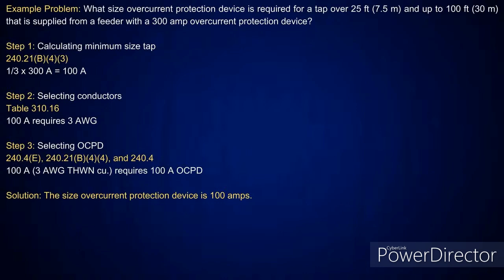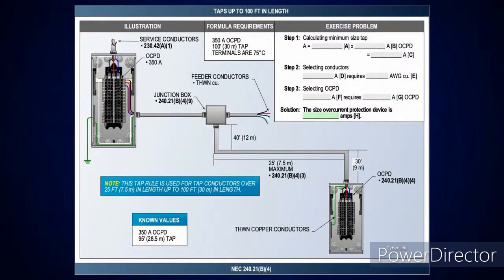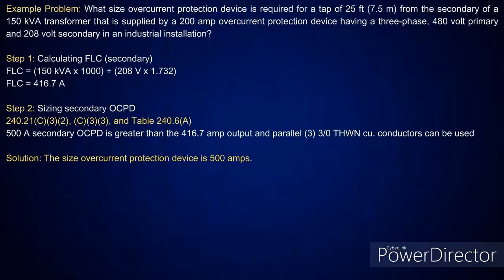That naturally matched up. So look, we've done a couple that didn't match, and we show you some that do match. Right. And we had an illustration just like this when we were doing the conductors, and all we're doing now is sizing the conductors and the overcurrent device to match. You've got a 350 amp overcurrent device upstream, take it to a third, get your amperage. Then once you have your amperage, know what your conductors are, and then size your overcurrent protection device accordingly at that point. Right. I want to go through these secondary conductors, and then we'll call it the night. There's a few of them.